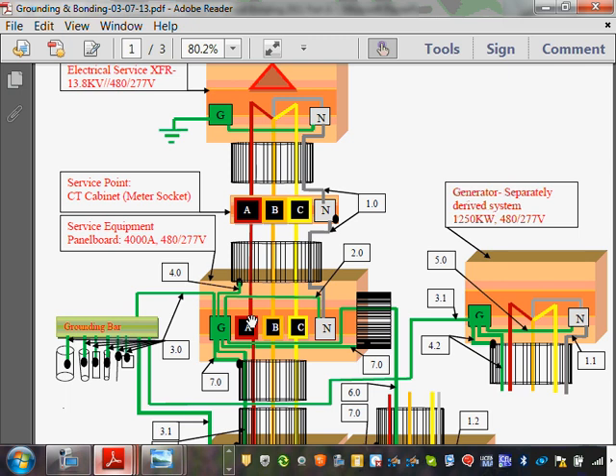For an open bottom switchgear, the only option that you have is a ground bushing or clamp. So you put the grounding bushing here, and you take a wire from here to the ground. How do you size that wire, and what's the name of that wire? The name of that wire, guys, is the supply side bonding jumper. See how the term is bonding jumper: you're tying the conduit to the ground. It's called supply side bonding jumper.